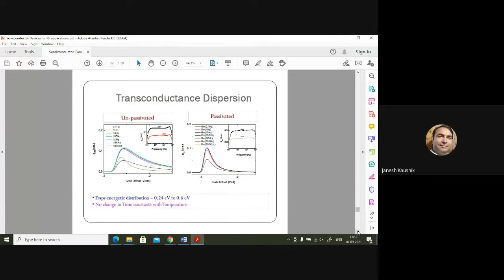So the device, sample one, that was giving very high gate leakage current and thermal activation energy in the gate leakage, gives a conductance DLTS peak of around 0.8 eV. But the broadness and the height variation of this conductance DLTS peak give the impression that these traps are distributed in nature and are somewhat different from the standard theory. So the peak of the DLTS signal is hole-like. If you compare the normal DLTS signal, it should have a positive peak, but here we are getting a negative peak, that is a hole-like emission. But actually there is no hole in this device, because totally the electron channel is present and nowhere else is there so much conduction. So it is actually a surface state. This is a special feature of surface state that comes into the DLTS signal as a hole emission signature.